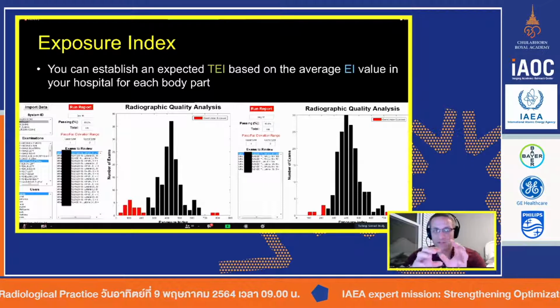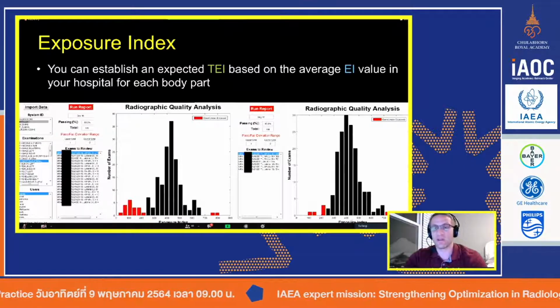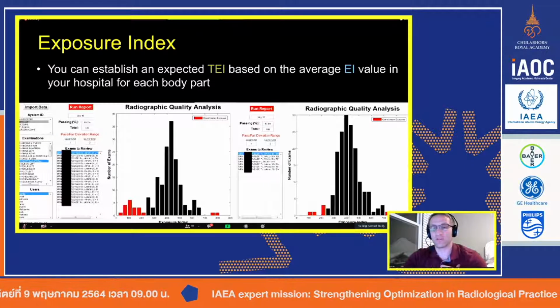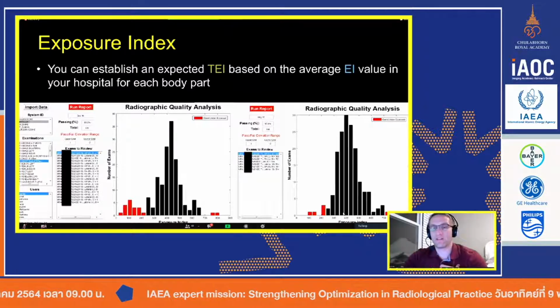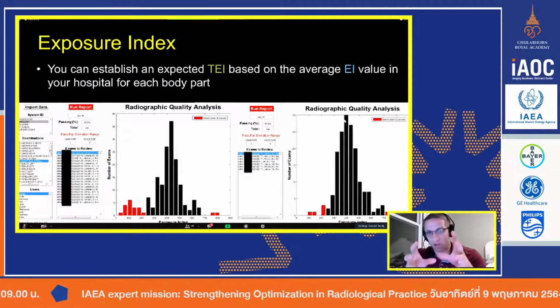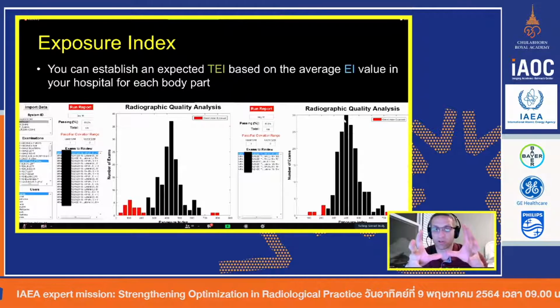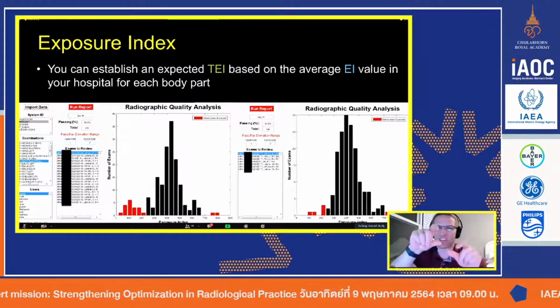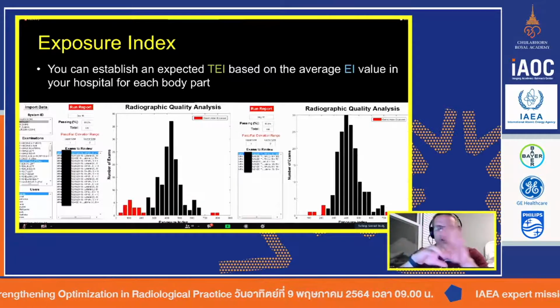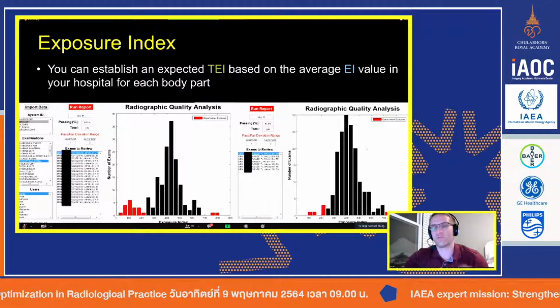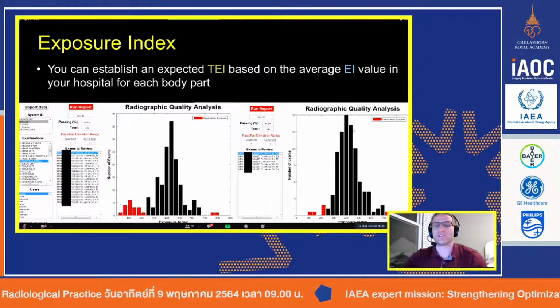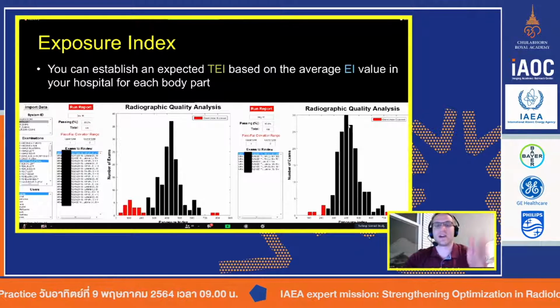In this particular vendor, they say a chest PA and lateral should be somewhere in the 400. In our case, when I worked with the radiologist and I got the image to look the way they wanted by setting the kV and the mA and all of that, the auto exposure control, all of that, it actually turned out to be about 420. And so that was my target. And you can see how it's basically the same.